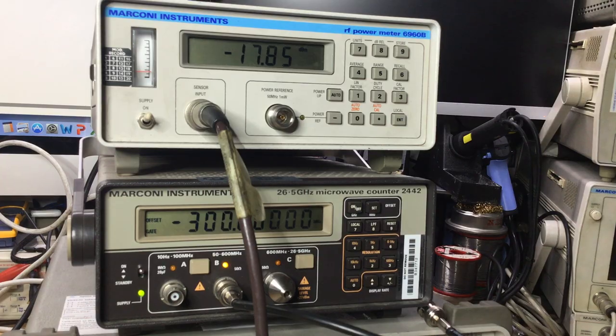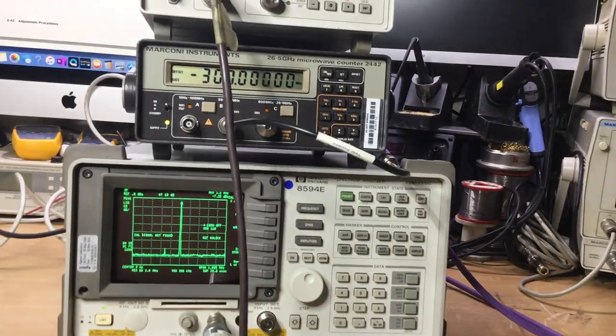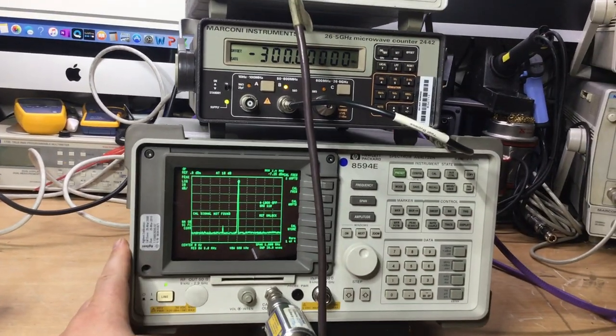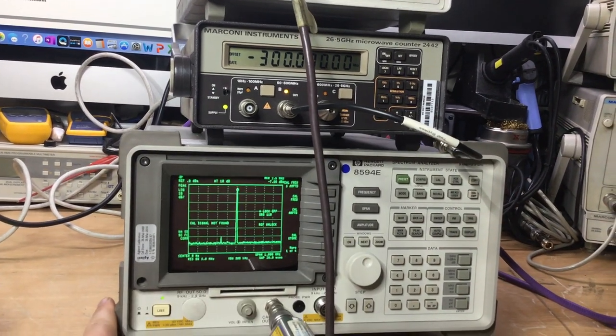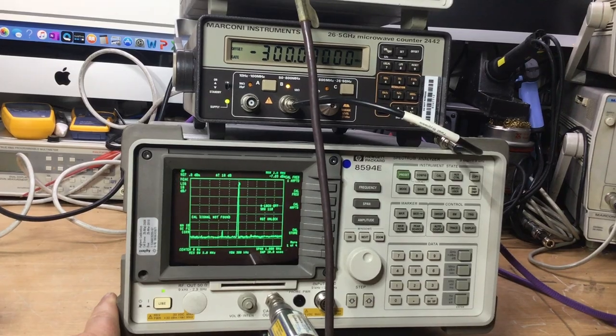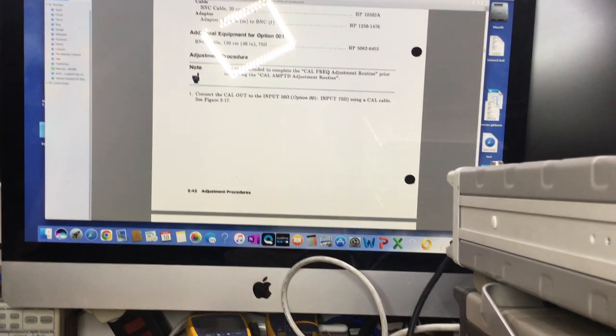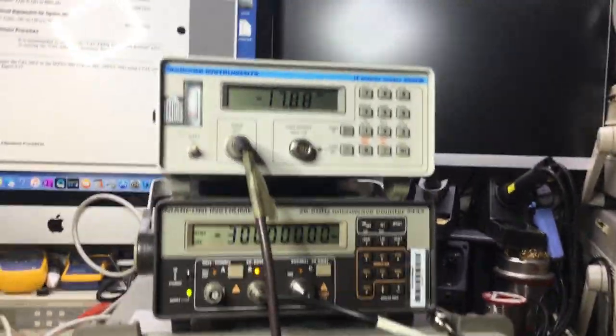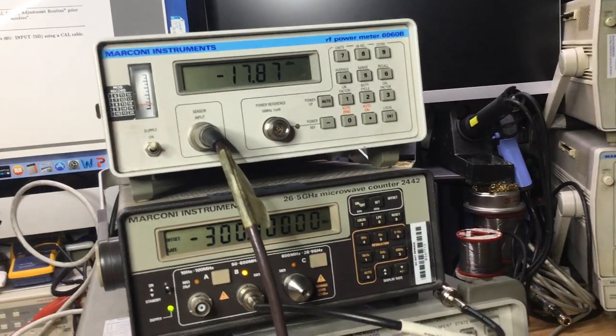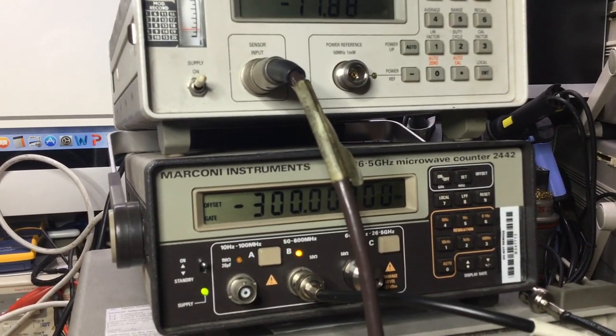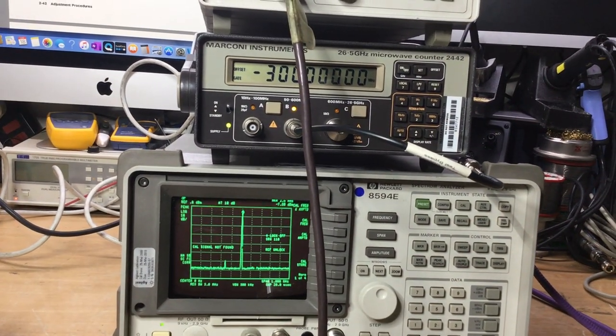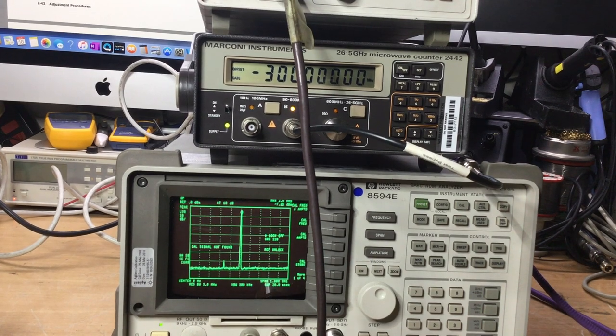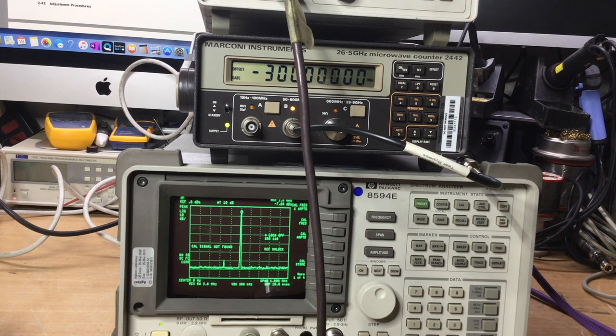So I think the first thing we need to do then is to whip the lid off this Agilent Spectrum Analyzer, and let's set up the frequency accuracy first, followed by the amplitude. Now it does mention here in the service manual something that I read earlier in an earlier section about being able to set the frequency accuracy up first before the level, if I remember rightly, not the other way around. So that's what we'll do. We'll get the lid off and we'll set that up first. Then we'll look at the level calibration and see what we can do about that, and hopefully we'll be able to get the calibrate working and take it from there.